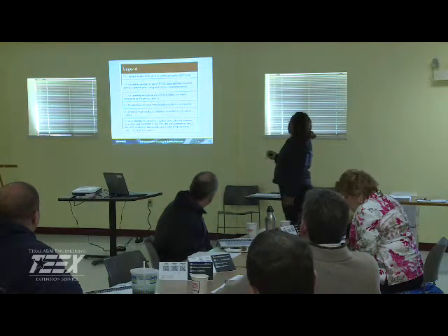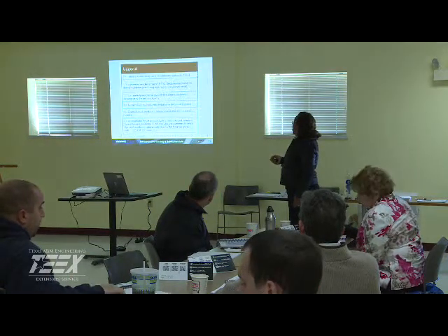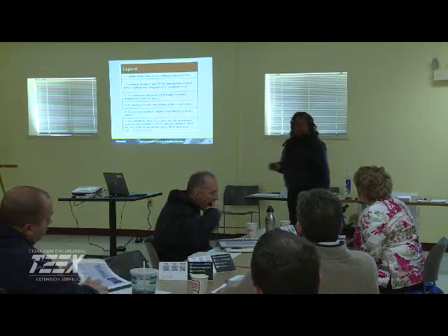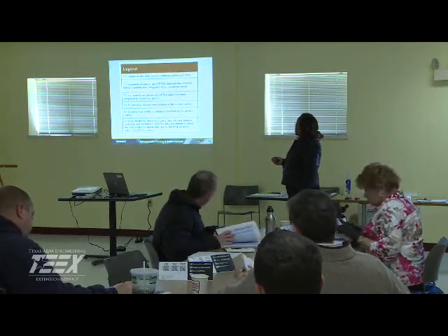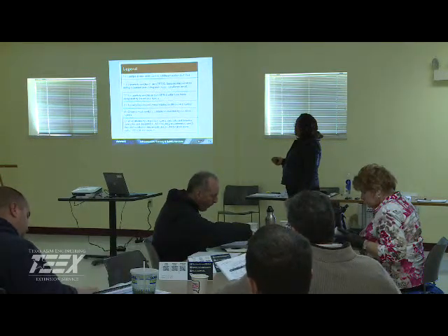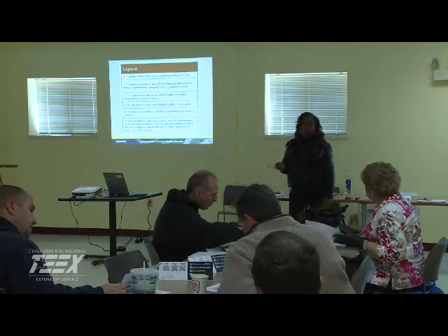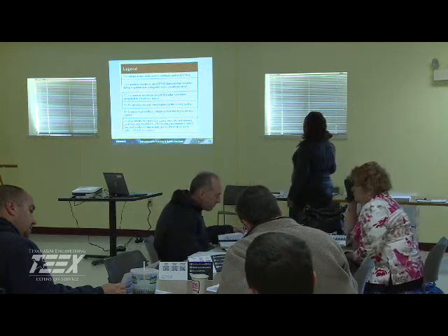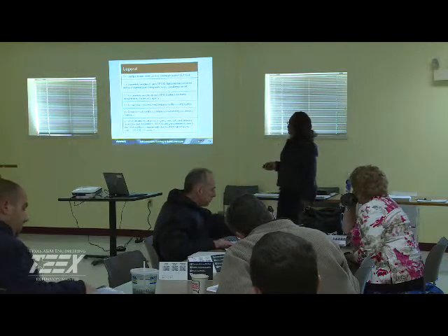All right, so when we get to this page here, you see the little asterisk. If there's one asterisk, that means one sample at each entry point to the distribution system is required. If there are 2, we need to do 2 quarterly samples at the entry, and they must be taken during 1 calendar year within each 3-year compliance period. If there's a 4, we're on a quarterly sampling basis. If there's an X, no sample is required unless specified by the primacy agency.